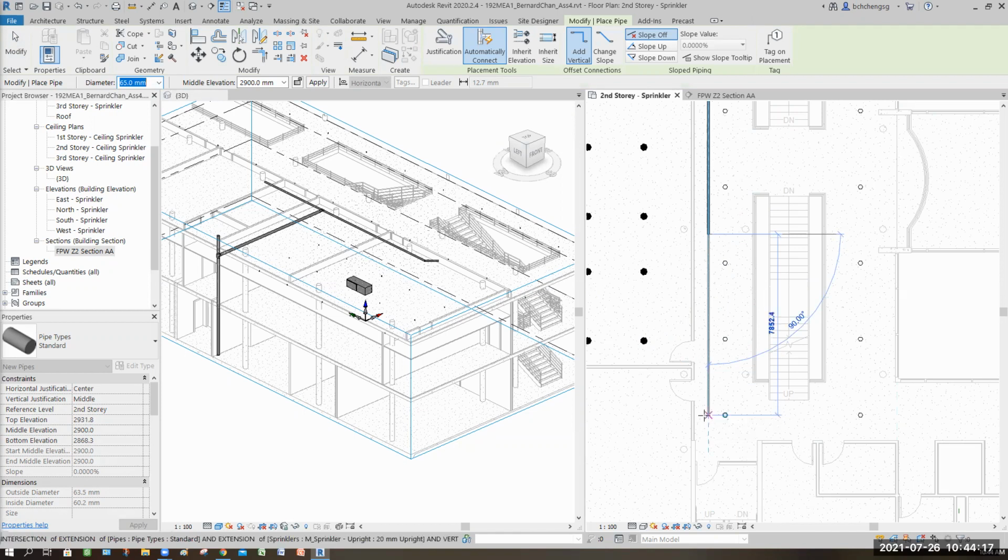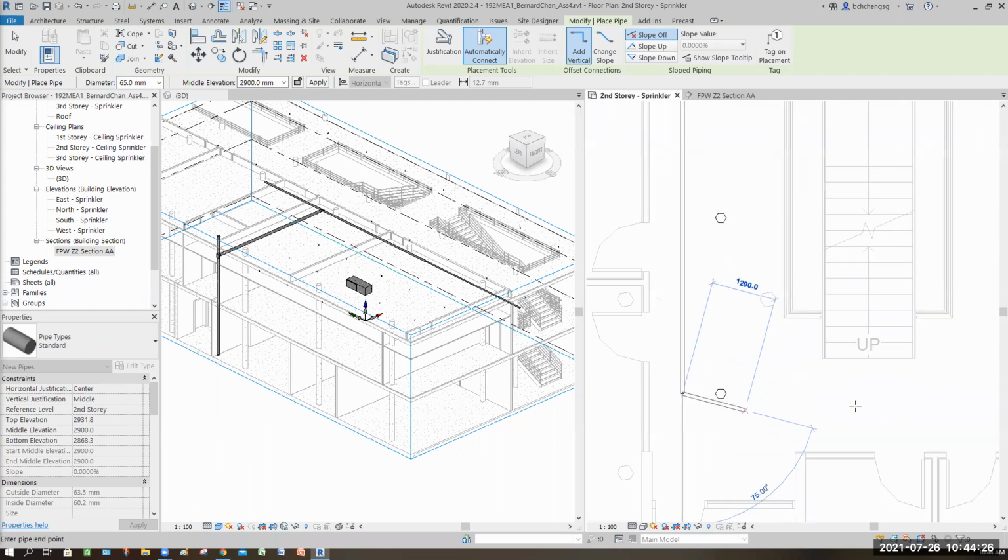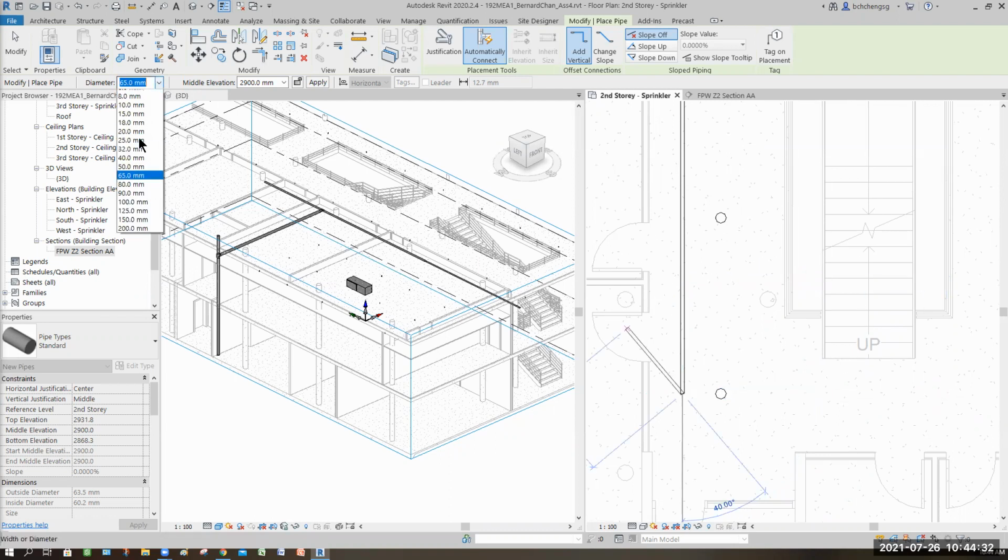Because when you stop here, you'll notice that later when you connect, it's easier. Okay, done. Then the pipe connecting to here is even smaller. The smallest pipe you can draw actually is 25 minimum, not 20. I see some of them minimum is 32. So it depends on your budget. Of course, smaller means pressure higher, definitely. Our sprinkler head is already 20 mm. So I'll use 32 for this case.